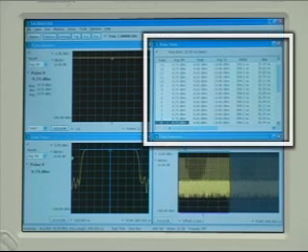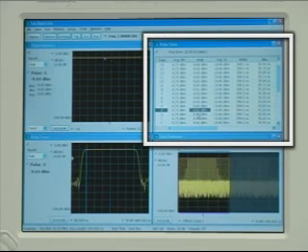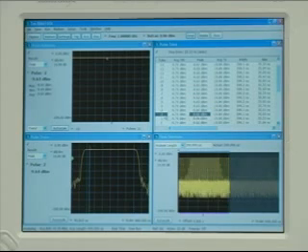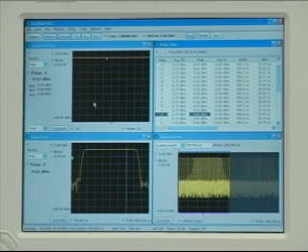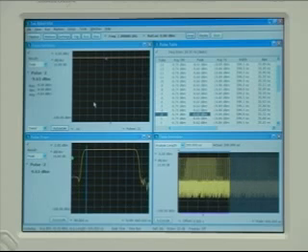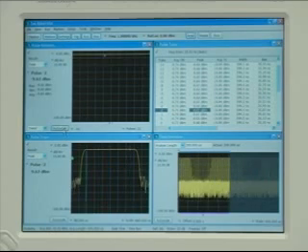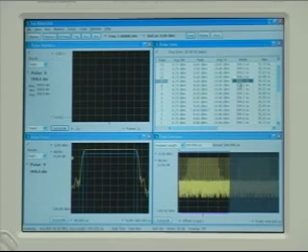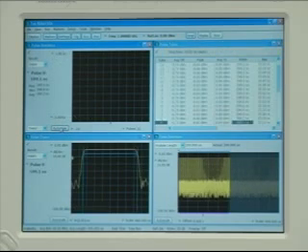The upper right display shows the result summary table, which is an indispensable part of the suite. This table indexes all the captured pulses, automatically measures all the key pulse parameters that have been activated by the user, and gives specific readouts for all pulses. The summary table is the raw data that essentially drives the other displays.